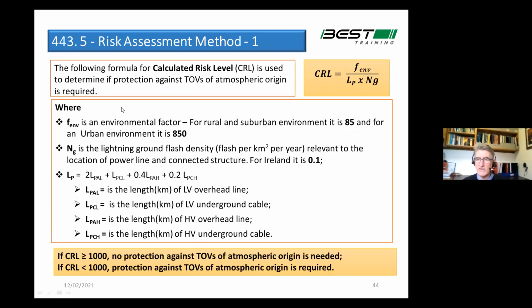So this is, I mentioned earlier on, the new risk assessment method for assessing whether you need SPDs or not. So the first thing I'll tell you about it, it lists a whole range of buildings that you definitely need SPDs in. For example, buildings where there's a risk of loss of life. So a hospital, okay, if you got a transient surge, could knock out a piece of life support equipment, that's clearly a risk of loss of life. Lots of other buildings, it gives you examples. Again, loss of cultural heritage, buildings, combustible materials, and all different sorts of examples it gives you where they are mandatory to put them in. There's no choice.